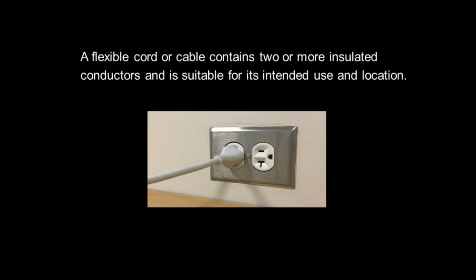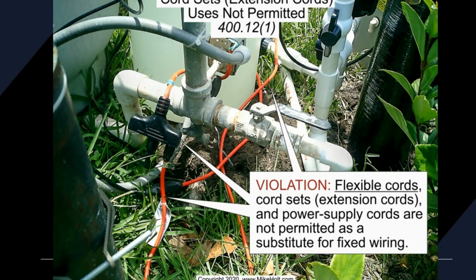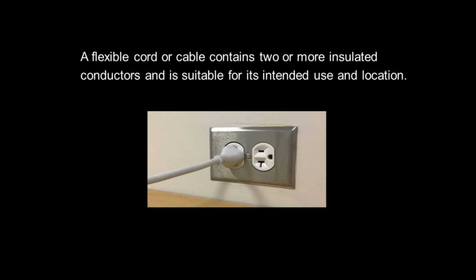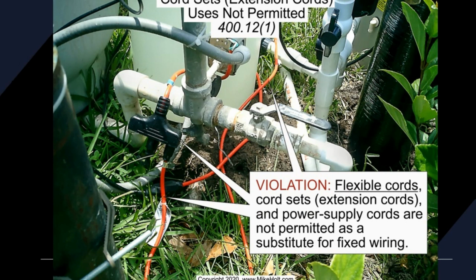All right. Flexible cords and cables contain 2 or more insulated conductors and are suitable for their intended use and location. Okay, so there's some things that we cannot do. We cannot use a cord or cable to feed a sub panel. I had a guy try to do that in a residence once. That did not make his day, showing him that code article. Flexible cords and cables and power supply cords are not permitted as a substitute for fixed wiring.